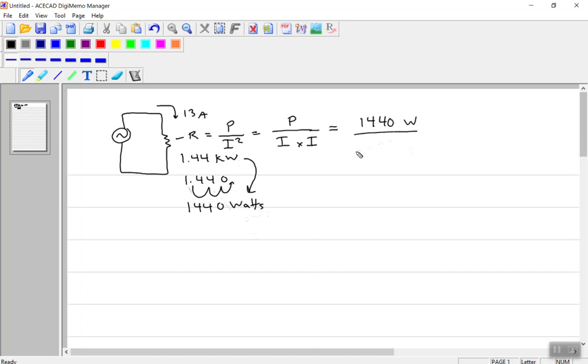And then the ampacity in this case was 13 amps. You can see it's drawn in here, right? So over here on the upper right, that's one of the givens, right? And the other given was down here, right? So I knew the ampacity and I knew power, so I can figure out what R is, okay? Power divided by I squared. So power, once again, was given in the question, as was ampacity, 13 amps times 13 amps, right? And then we just simplify here using our calculator.